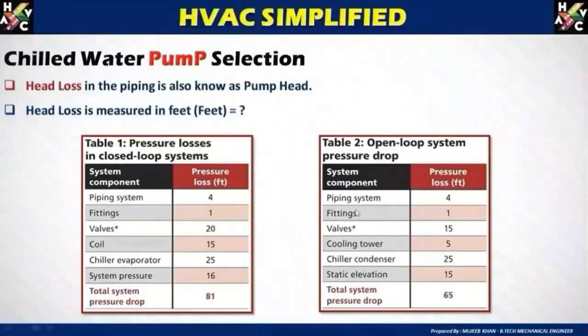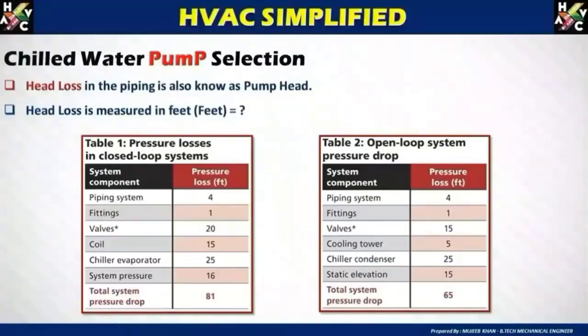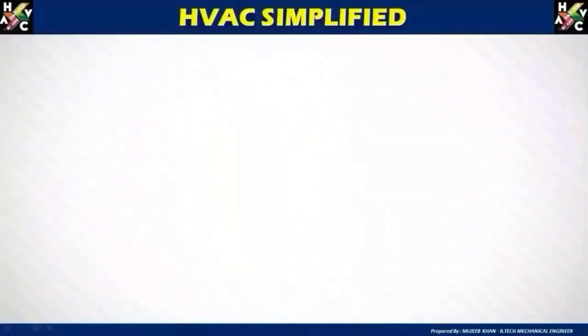The parameters to be considered for pressure loss in a closed loop system are: piping system, fittings, valves, coils, and chiller evaporator. In an open loop system, you consider: piping system, fittings, valves, cooling tower, chiller condenser — and static elevation is an added parameter which must be considered in an open loop system.